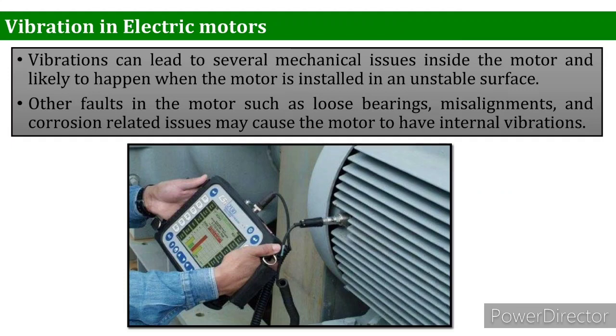There are also some mechanical conditions which can put our electric motor in a serious condition. Vibration is one of them. Vibration can lead to several mechanical issues inside the motors and is likely to happen when the motor is installed on an unstable surface. Other faults in motors, such as loose bearings, misalignments and corrosion related issues, may cause the motor to have internal vibration. As you can see from the picture, a man is measuring the vibration of a big motor. If the vibration exceeds a certain value, the rotor gets damaged because the alignment of the rotor gets mismatched.